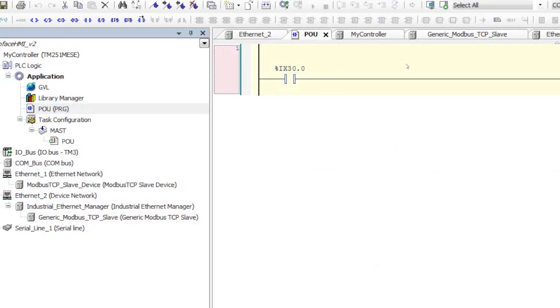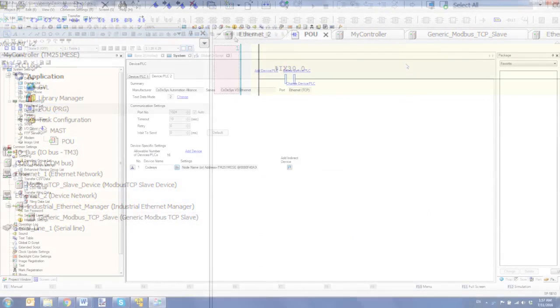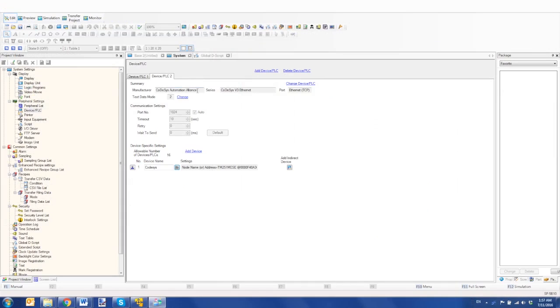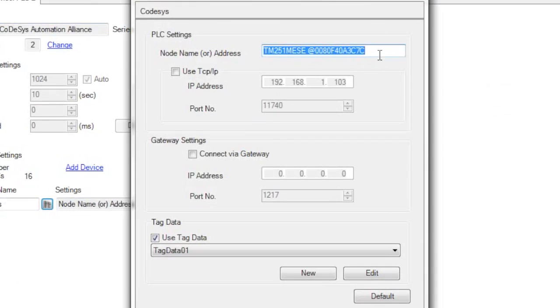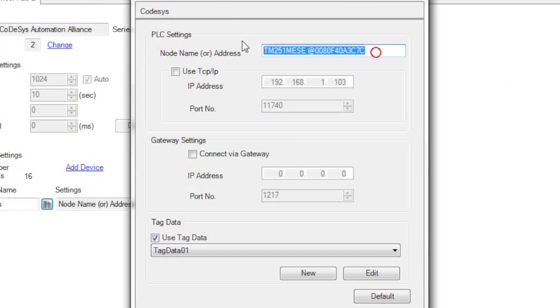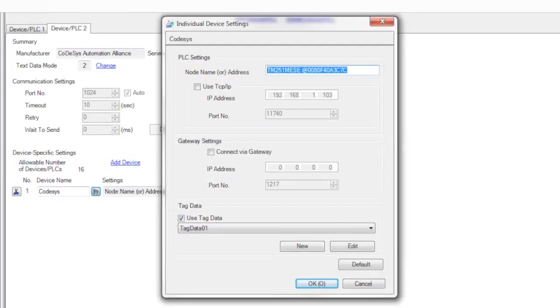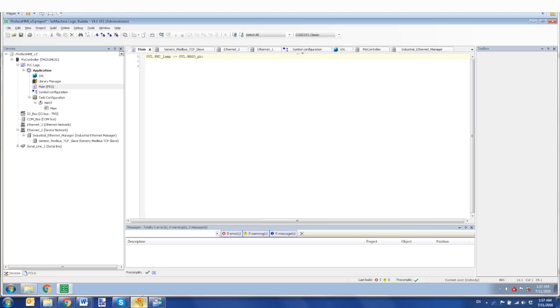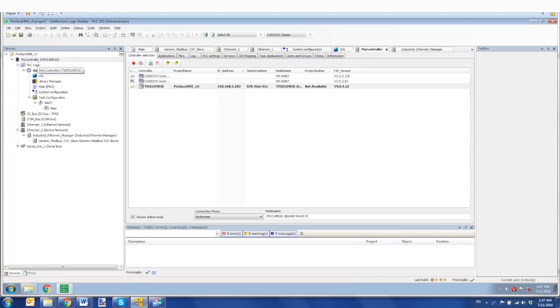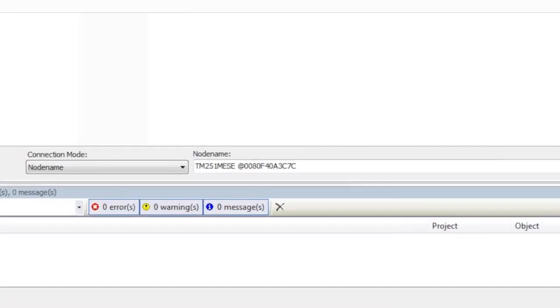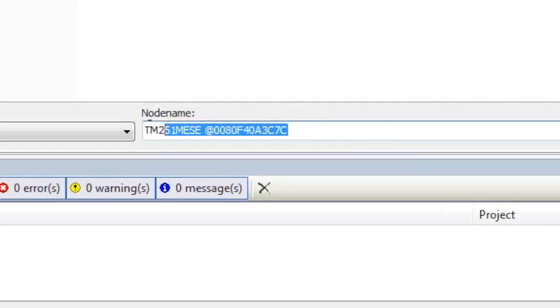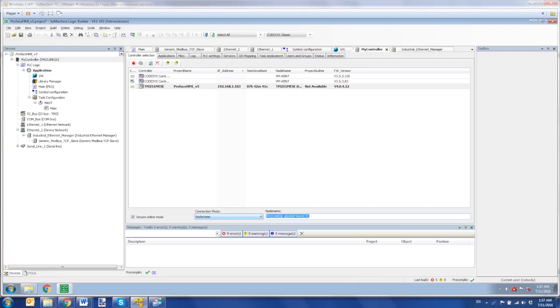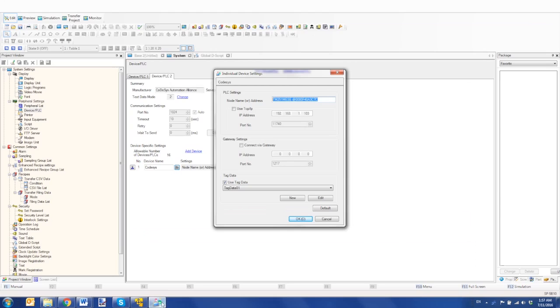The second example I'm going to show you is using the tag database over CoDeSys. For the CoDeSys setup to share the XML file, I have given a name of CoDeSys. And if I select this, I can input its node name or I can access over its IP address. I'm using the node name. And I found that in the SoMachine software. If you go to my controller, when you're connected, you can copy and paste the node name out of here and bring that into the ProFace software.